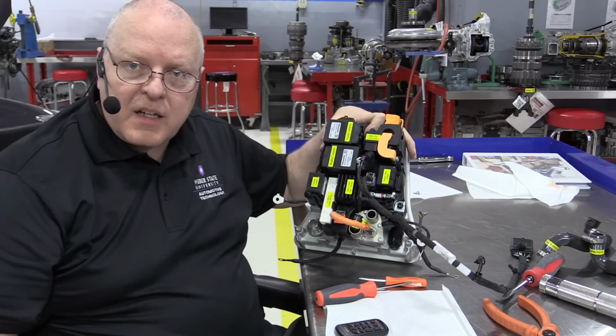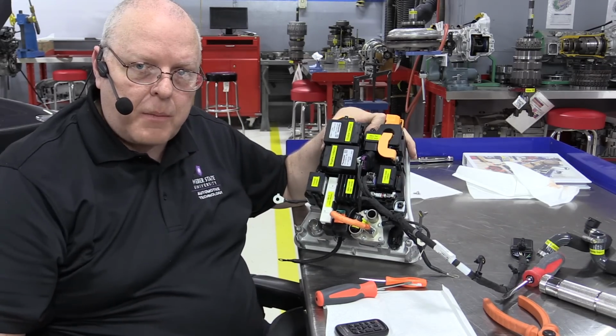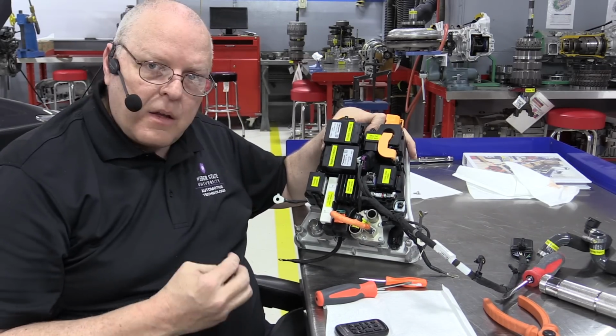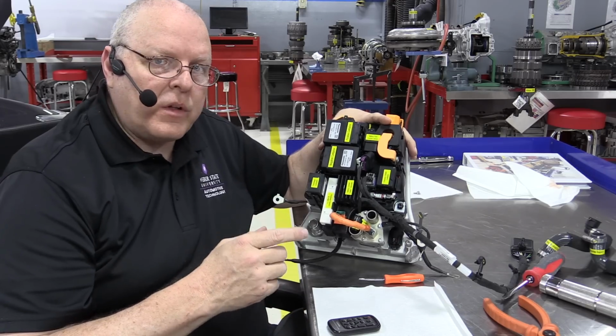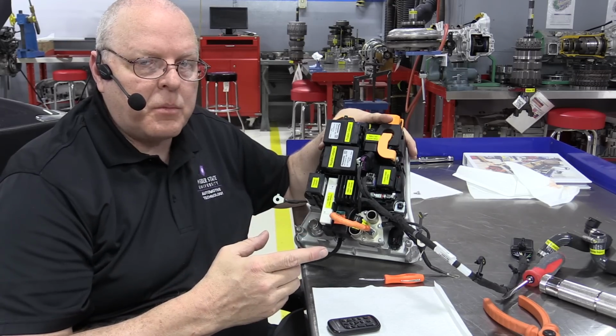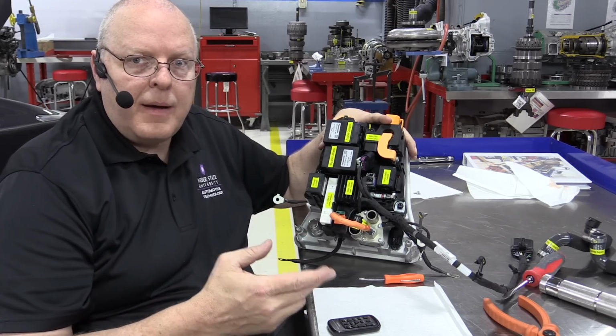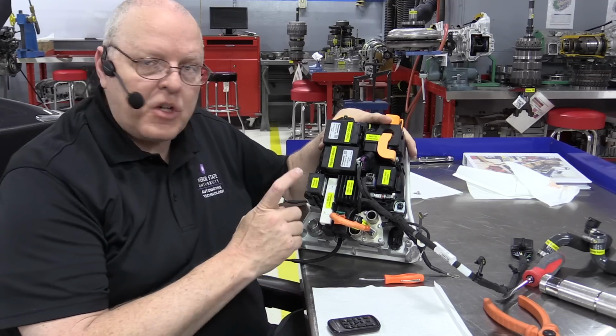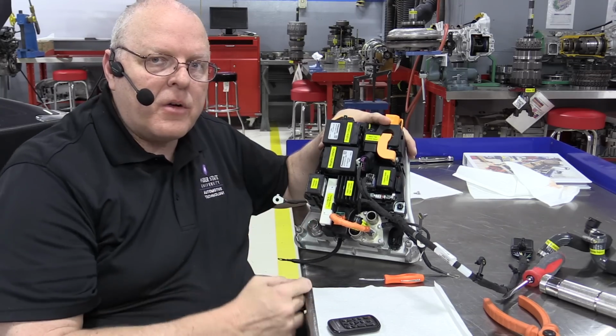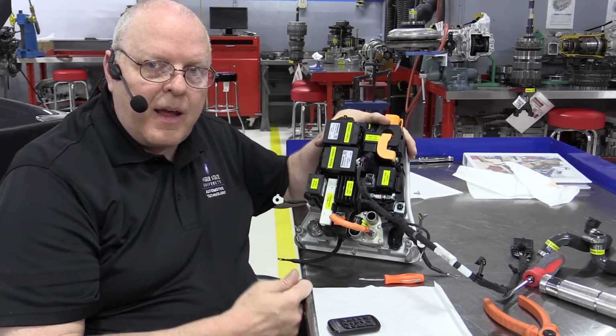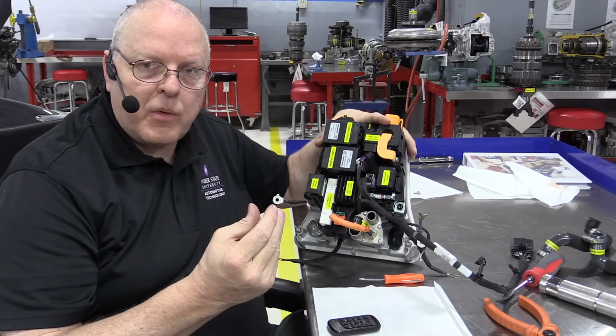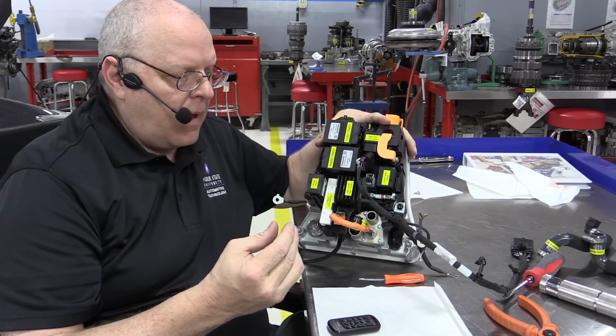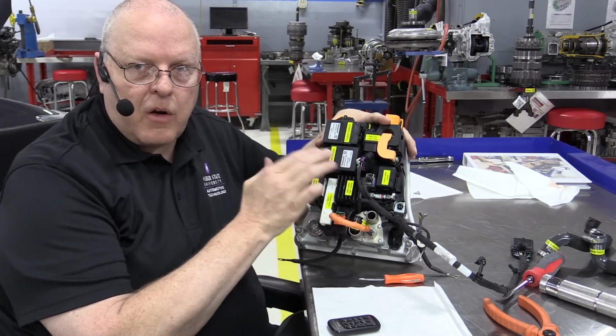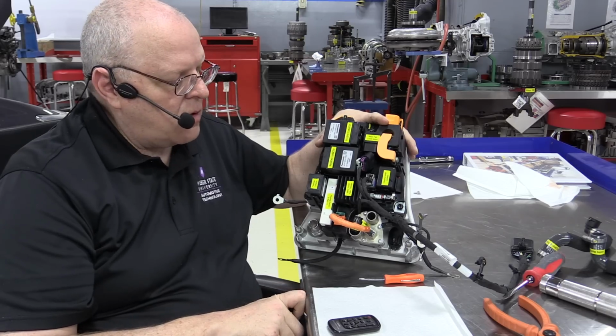big smoothing capacitor inside of the inverter on top of the transmission. And when it gets charged, the voltage on the negative terminal of that smoothing capacitor will be 0, which will be the same voltage as the negative contactor ground side, and we can close the negative contactor with no voltage differential, and it won't arc and destroy the contactor sooner than necessary.